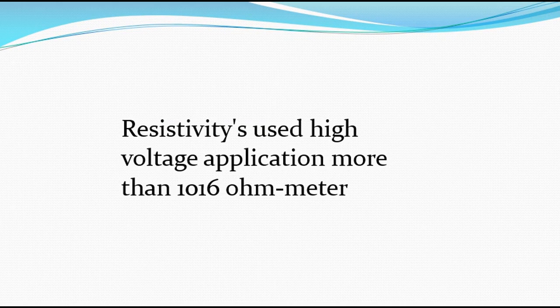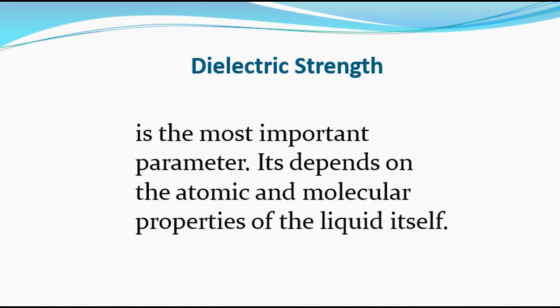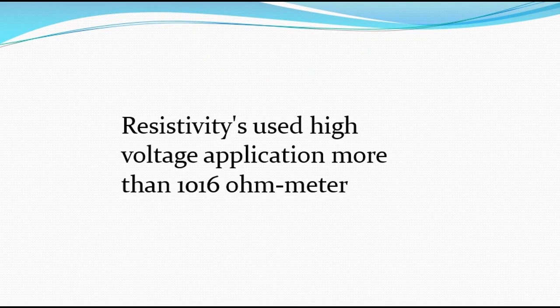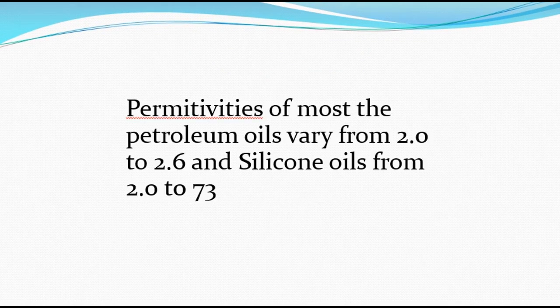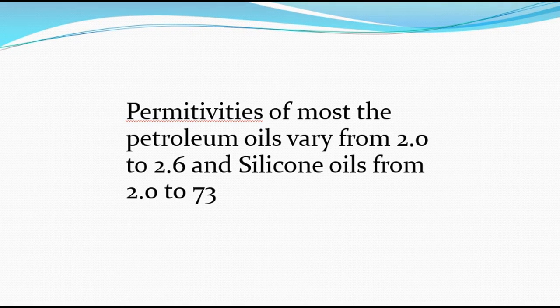Resistivity, for high voltage applications, is more than 10 raised to power 16 ohms meter. In terms of permittivity: most petroleum oil ranges from 2.0 to 2.6, while silicone oil ranges from 2.0 to 73. When I discussed silicone oil previously, I showed you the image of it and explained how it works and functions.